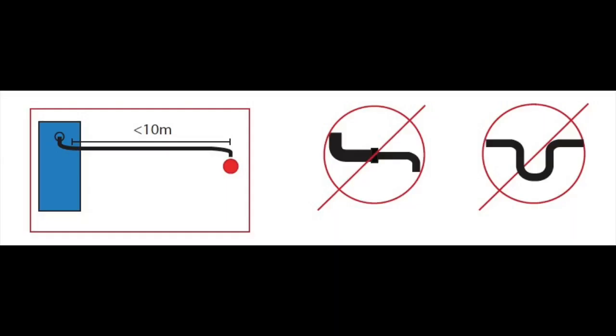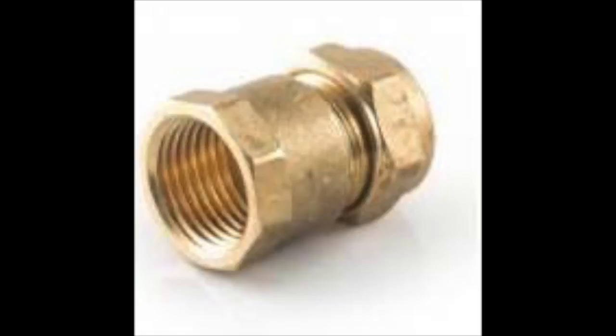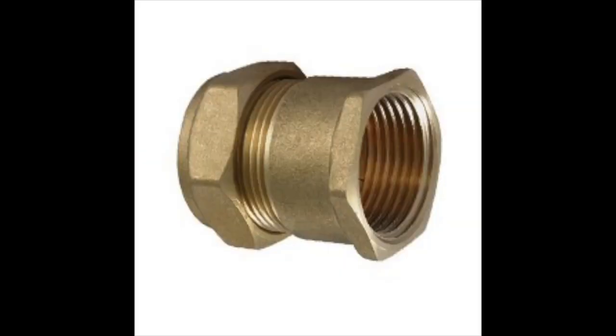Steam pipe. You should not run the steam pipe any further than 10 meters from the steam generator to the room and anything above three meters should be insulated. The steam pipe should not be reduced from the outlet size. For example, in England we use 15 millimeter for half inch or 22 millimeter for three quarter inch.